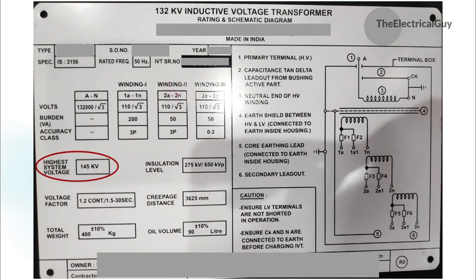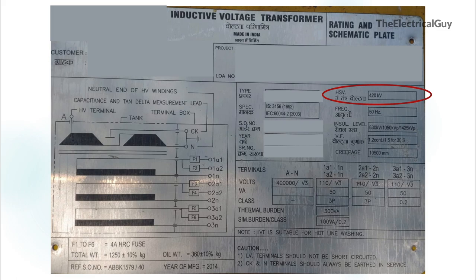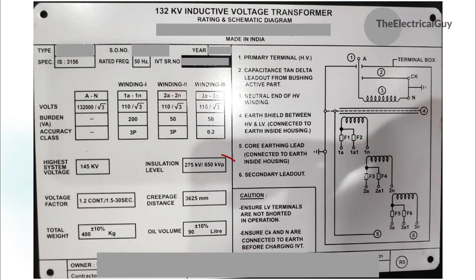Moving on, the highest system voltage or HSV is 145kV. This is the voltage which can be sustained in the system at any time and at any point. You may ask what is 132kV — well, 132kV is the nominal system voltage for which the system is designed. This is where most people get confused: 145kV is the highest system voltage and 132kV is the nominal or normal system voltage. Similarly, on other nameplates, 36kV is HSV and 33kV is nominal; 420kV is HSV and 400kV is nominal.